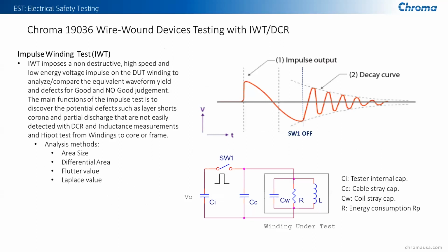Impulse winding test is a very unique test. The way that we do this is we actually inject or impose a charged capacitor across the actual inductor of the winding. And when this occurs, it creates a ringing. And with the ringing effect, we can do a high-speed analysis of the ringing of the voltage. And during that time, we can see various types of changes when we compare it to a known good part. These changes include things such as the area size, the differential area, flutter value, and what we refer to as Laplace value. And I'll go into those in a little more detail.